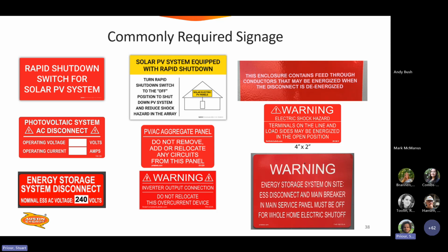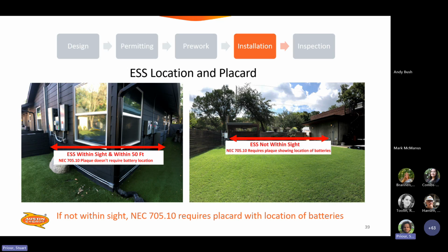We also have a label on the bottom right there about energy storage system on site. It's telling someone that in order to do a full home shut off, you'll need to kill the main breaker and an additional ESS disconnect. So, energy storage system location and placard. If it's within sight and within 50 feet of the main disconnect, you don't need a placard according to NEC 705.10. If it's not within sight, you do need a permanent placard that is oriented properly at the main service location, showing the location of those batteries. So the placard being oriented properly is kind of important. You should be able to look at that service and immediately point to where the ESS are. Shouldn't have to crane your neck and think too hard.